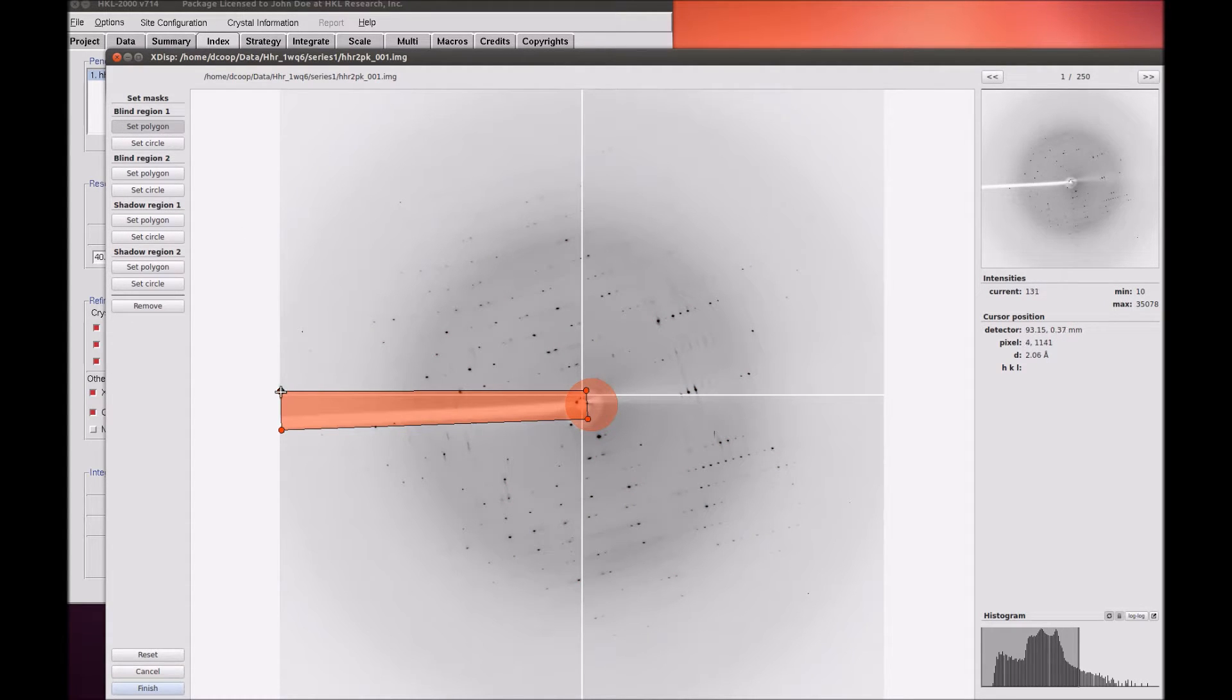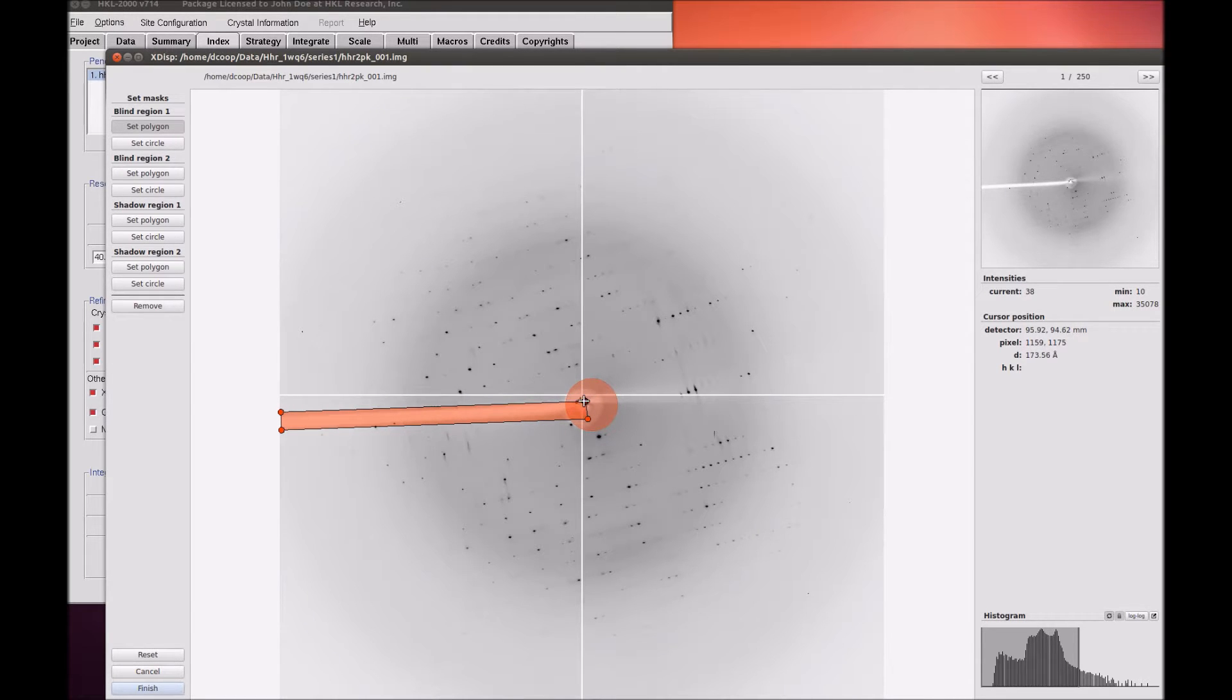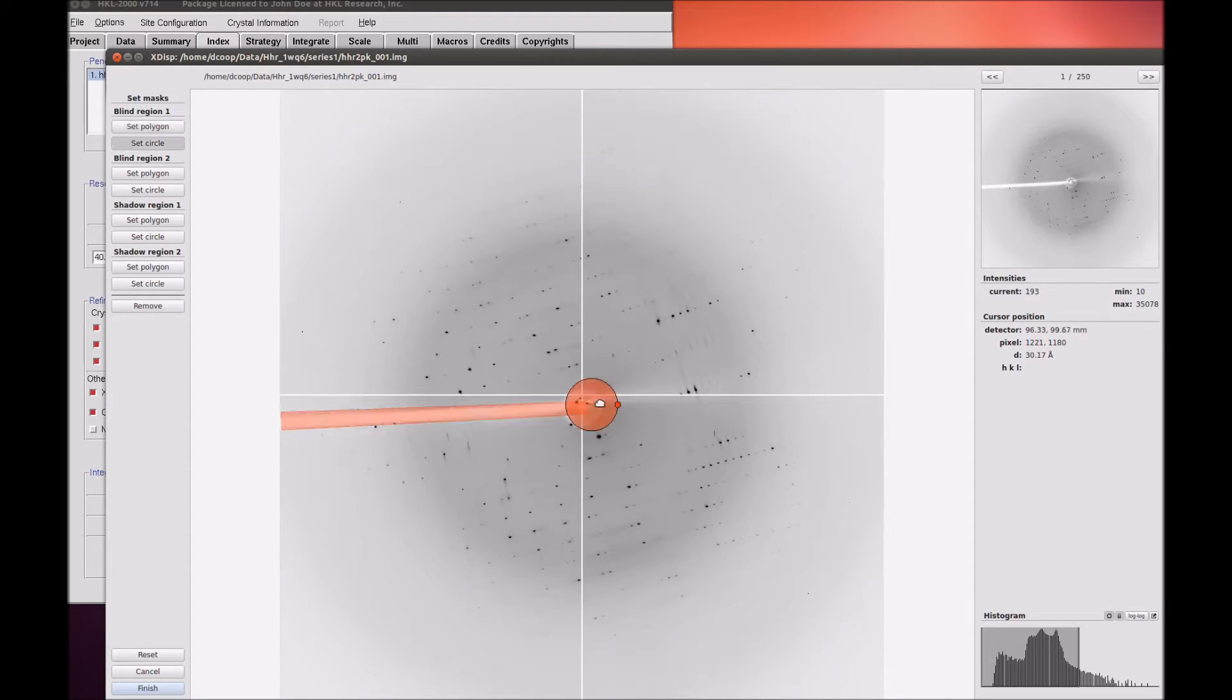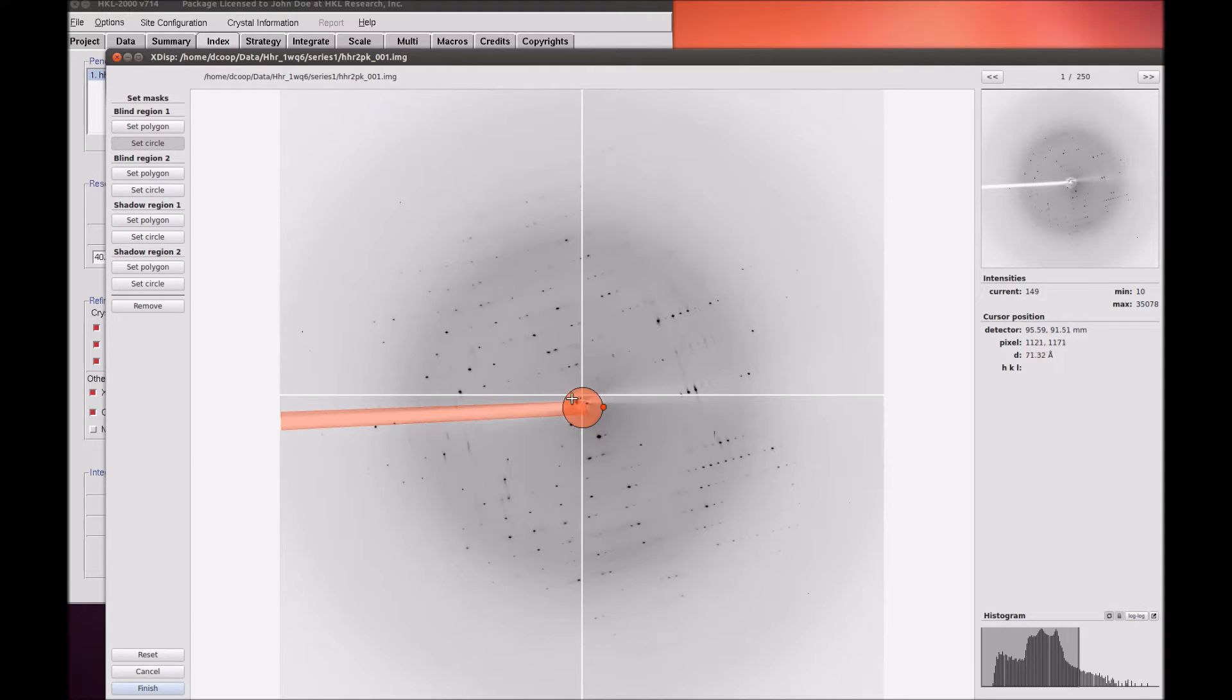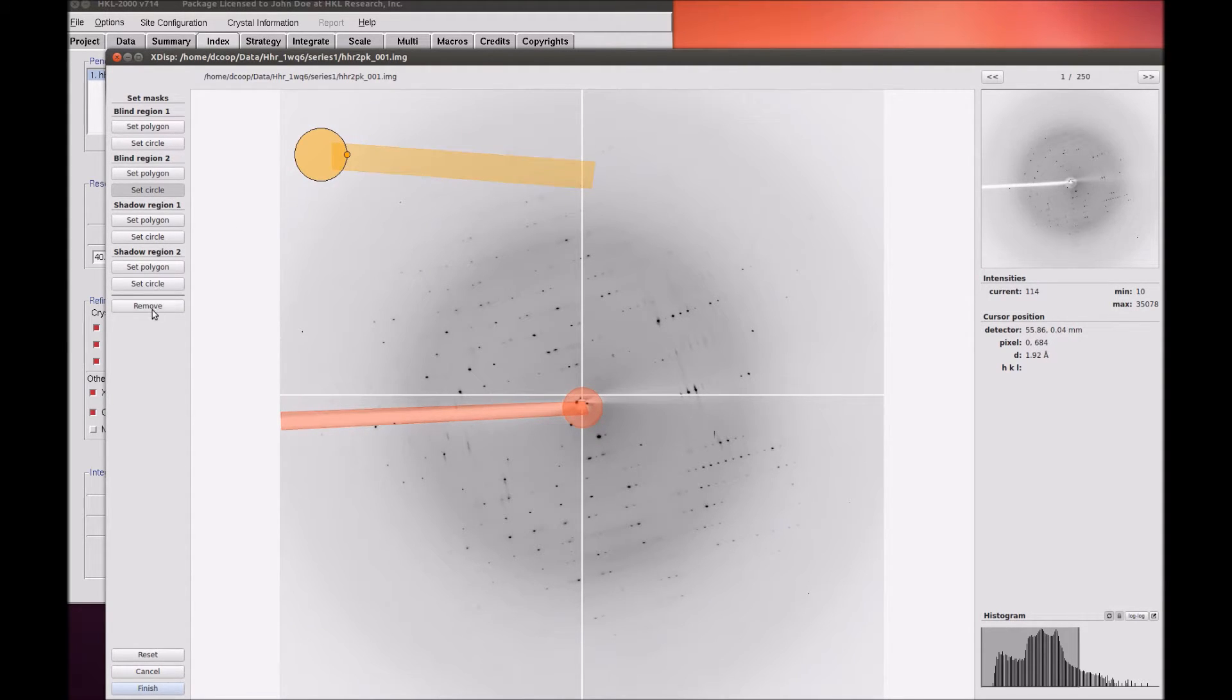The Edit Mask button provides an easy and intuitive way to define the beam stop, or flag regions where a shadow appears on the image. To use this feature, click on a polygon and the corners appear as circles that can be dragged to fit the beam stop shadow. Circular regions have a single control circle on the edge that changes the diameter. The shapes can be moved by clicking inside the shape and dragging it to a new location. More than one mask can be created. To delete a mask, select it and then remove it. Click Finish when you're done.